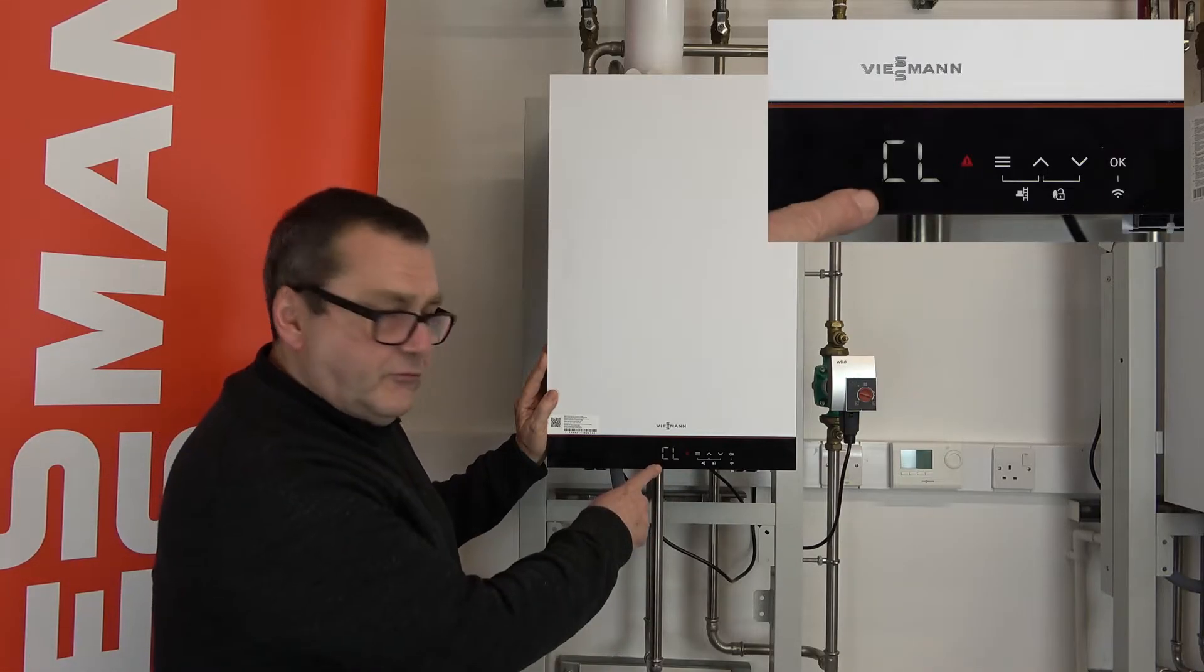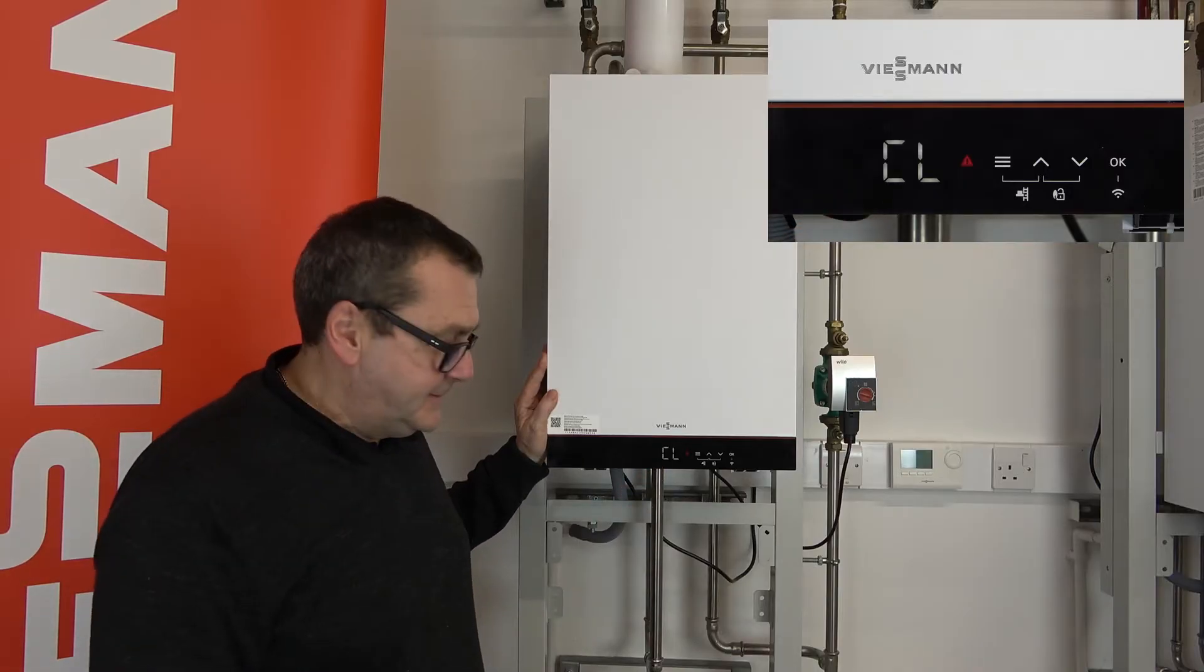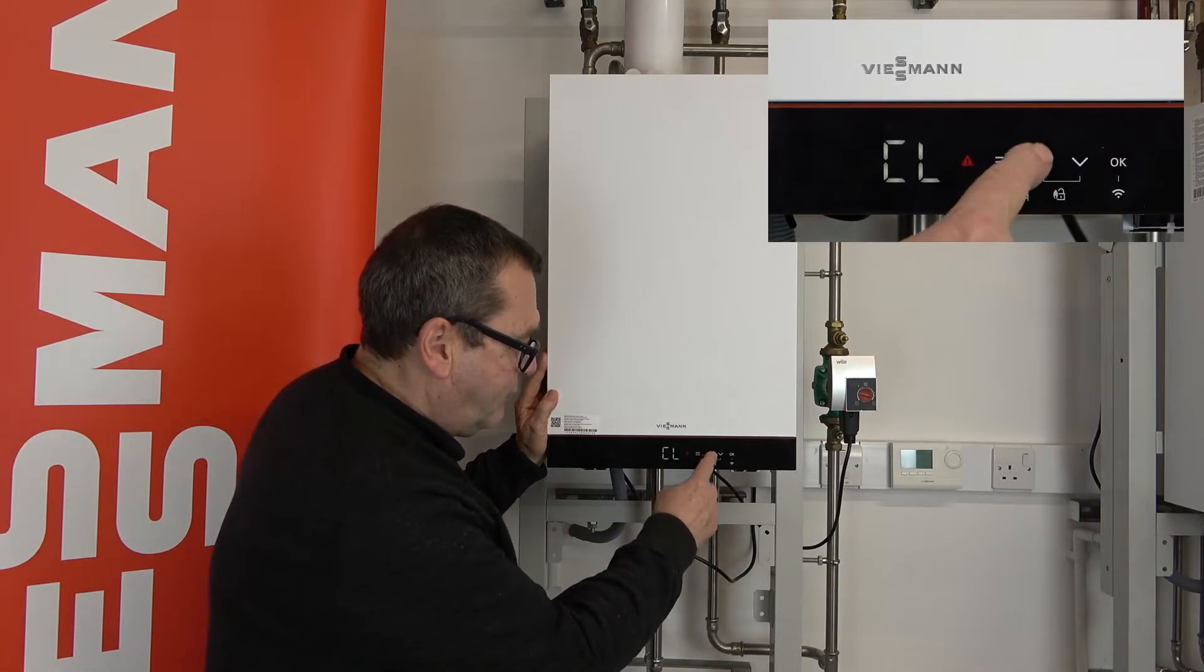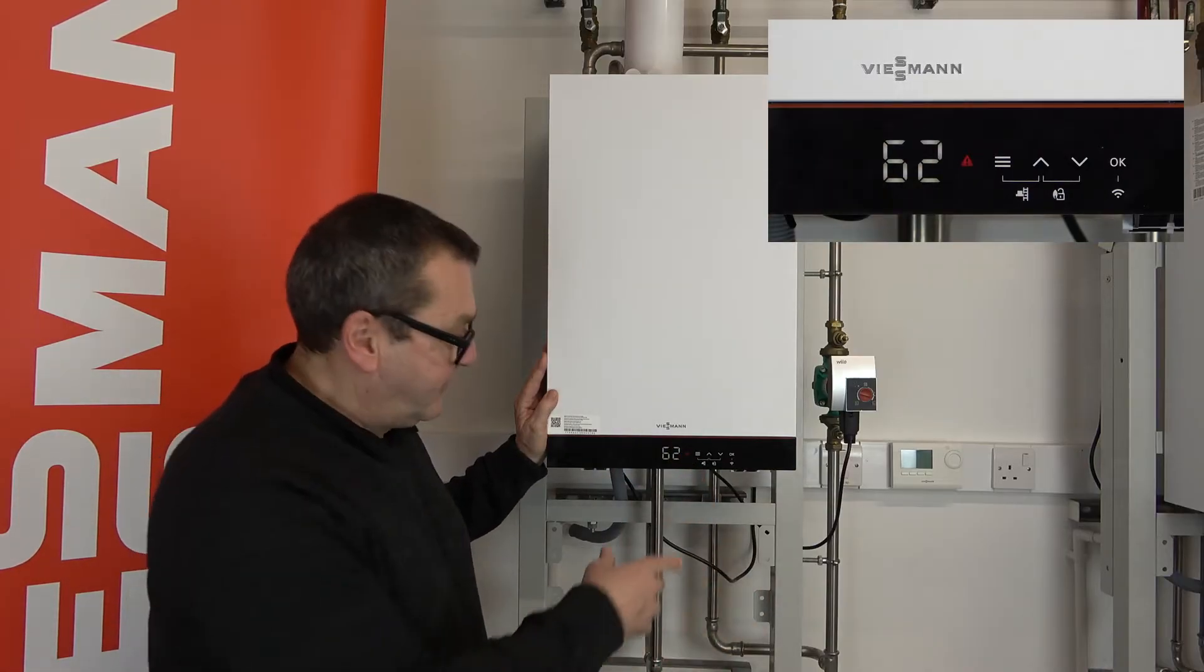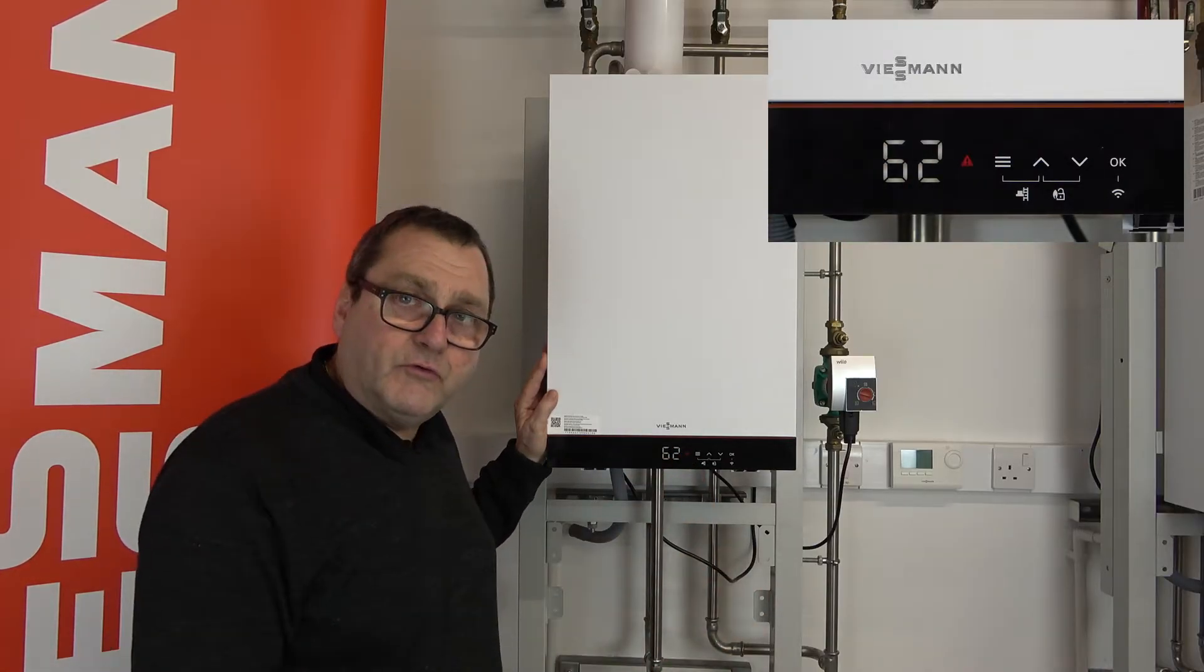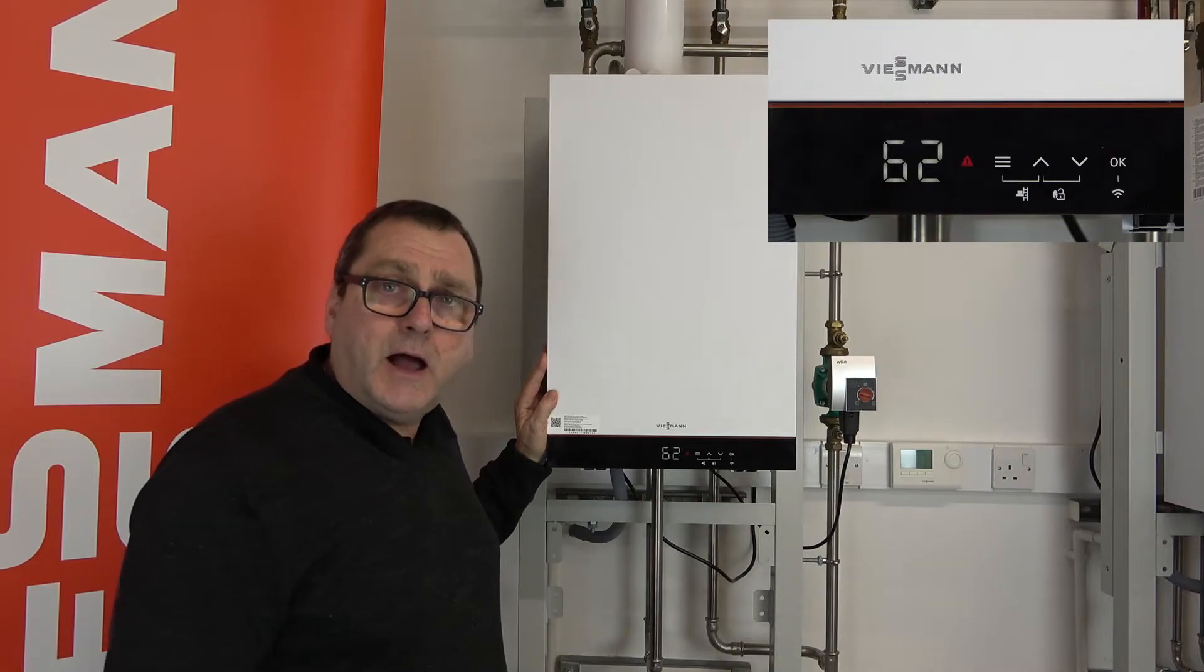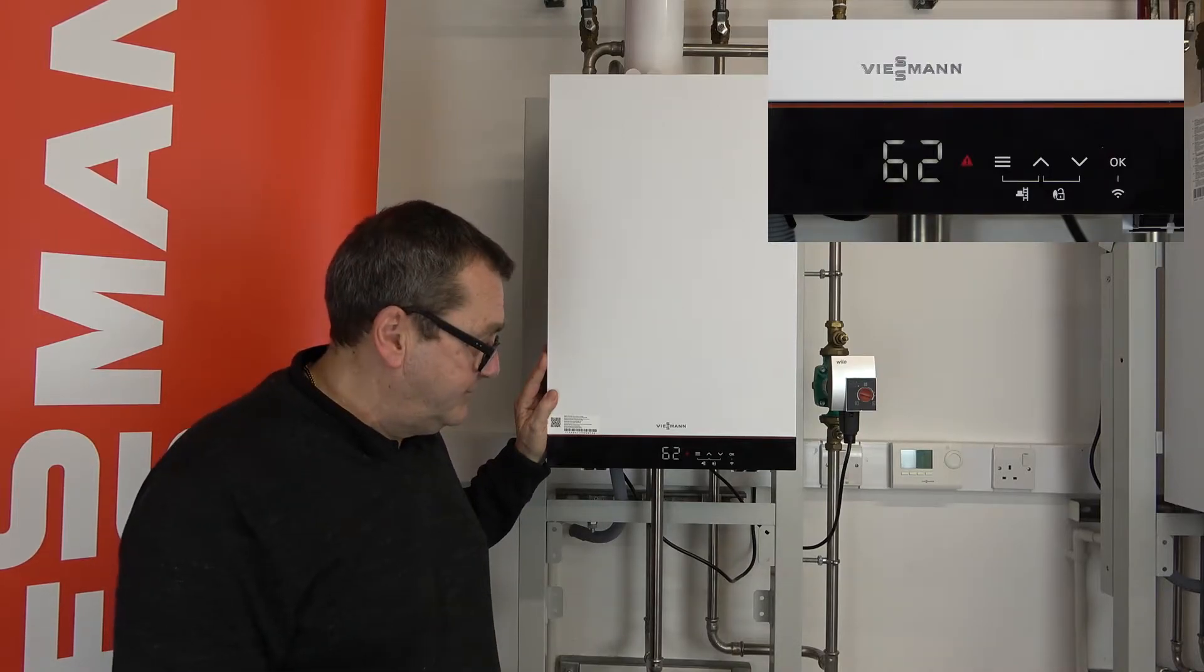You can see that on the front display we have CL displayed. To actually find out what that fault is we can press the up or down arrows and we can see here number 62 comes up, which means that it's a high limit fault. The boiler is overheated for some reason.